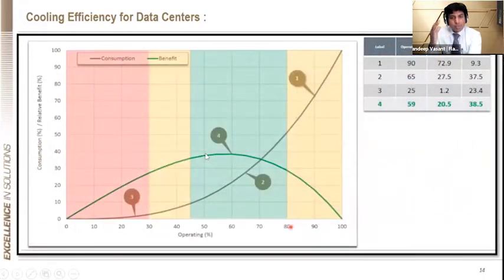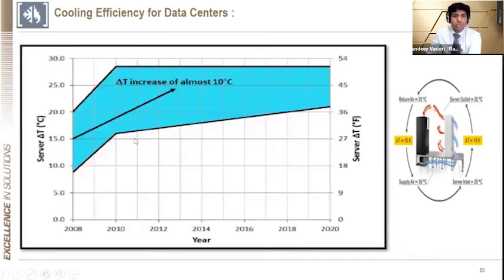Not only that, once we select the most efficient components, let us say we have a requirement of 10 TR into 5 and the 5th unit is a standby. Thanks to the inverter compressor and the EC fan, it's better that you run at part load. Rather than keeping the 5th unit as a standby, it's better that you run all 5 units at partial load to meet your requirement of 10 TR. What happens in that scenario? If you see, as per the cube root formula, if you run at 100%, the power consumption would be 100%. As you drop, thanks to the variable inverter compressor and EC fan, the power consumption at part load would be less. Thereby, if you see here, operating the units at 60%, power consumption would be 20%, not 59, and thereby you get the benefit of saving close to 38%, not only in the PAC but also in the chillers which go into the data center. So this is one modification or suggestion that you can make.